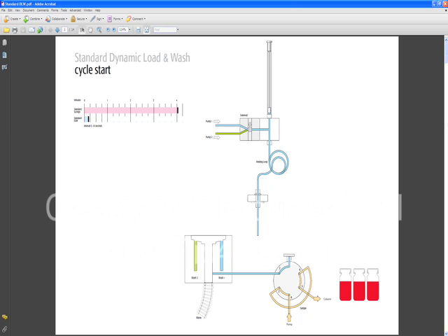You see on the screen the syringe which is sitting on top of what we refer to as the retention tubing which connects to the needle. You see coming in from the left side from the pumps solvent one and two. And you see the solenoid valve that can switch the solvents. On the bottom on the left you see the wash station which are basically fountain type wash stations which are passive. Sample vials are to your right. We'll step through this cycle so you can see what each individual step is.